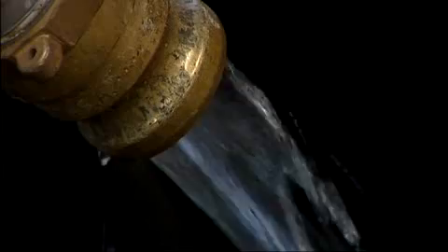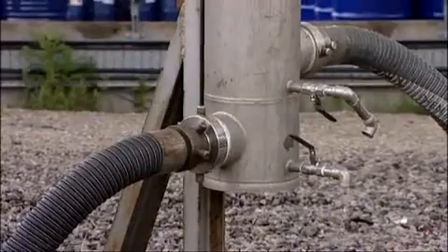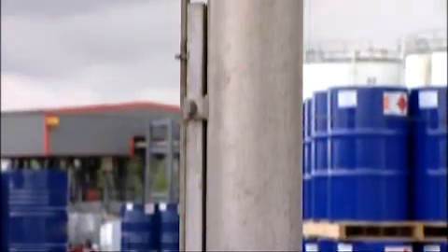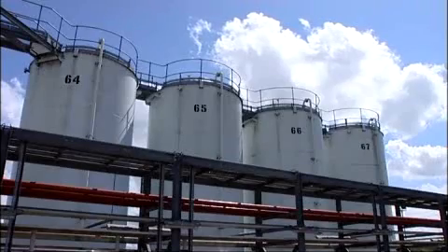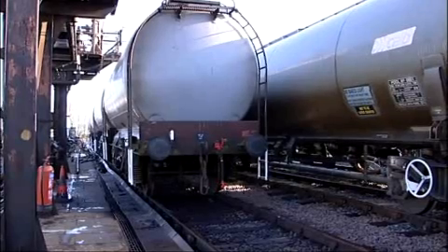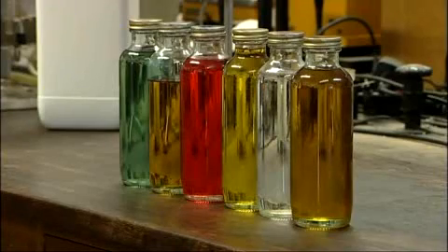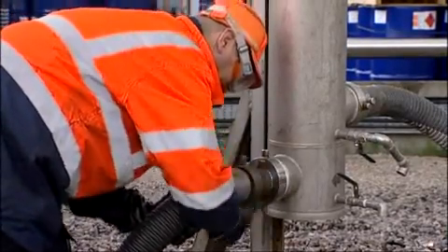Static electricity charge can be generated in solvents by liquid movement such as flow, mixing, pouring, pumping, filtering, or agitation operations, where the movement separates electrical charges which may accumulate in the liquid and the containment system, such as pipes, tanks, drums, road tankers, rail cars, and ships. If either of the materials is a good insulator, or the plant is isolated from earth, electrostatic charge will accumulate.